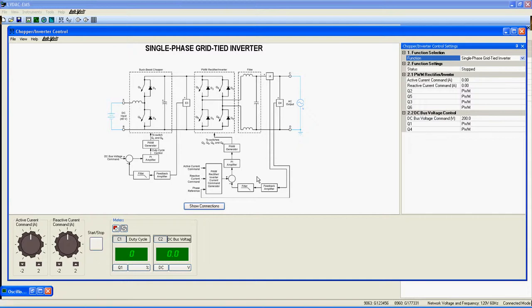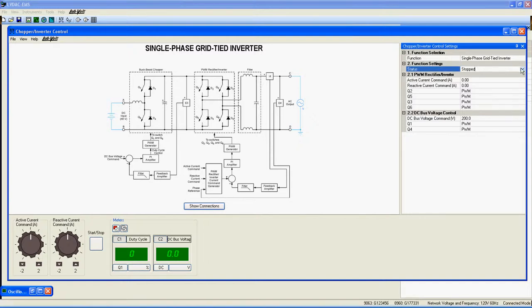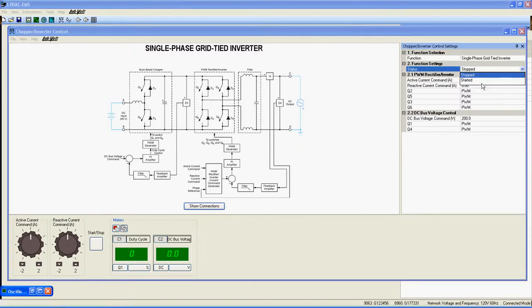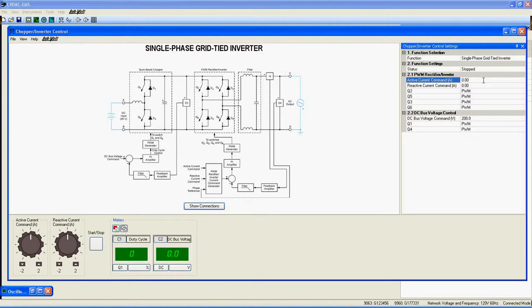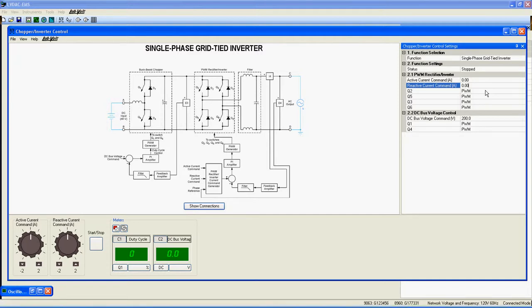Now go here under Function Settings to see all the features available for this function. Status indicates if the function is started or not. In the PWM Rectifier Inverter Settings, we get Active Current command, which sets the desired active output current, and Reactive Current command, which sets the desired reactive output current.